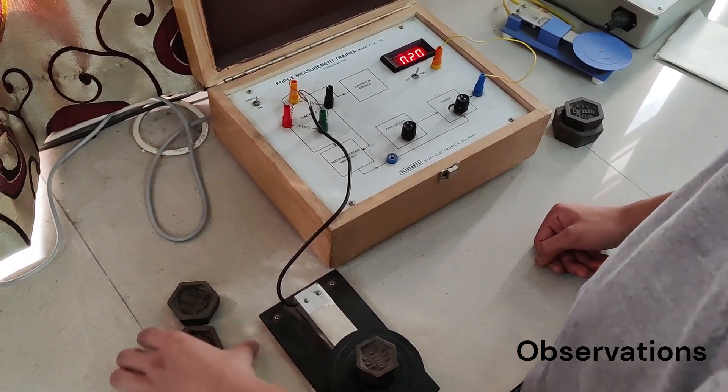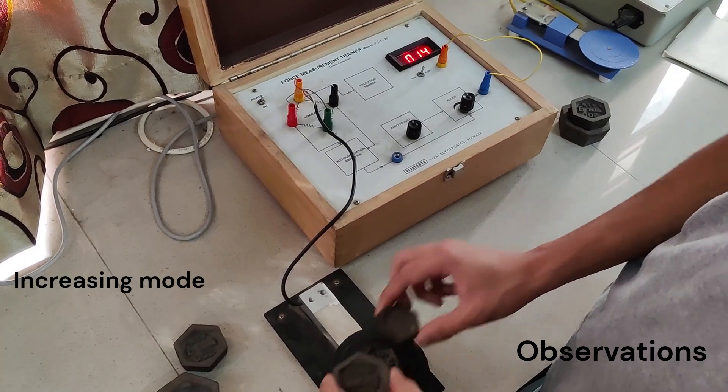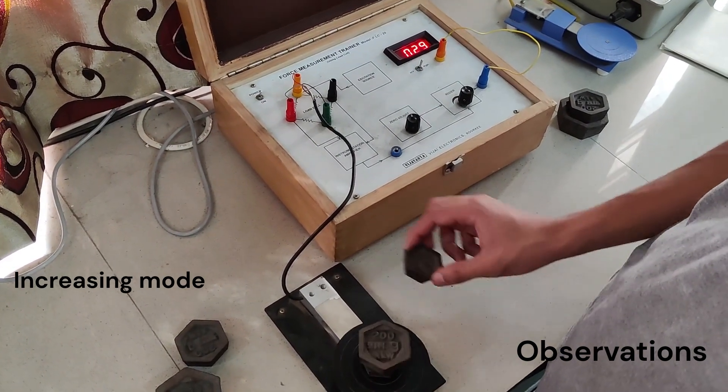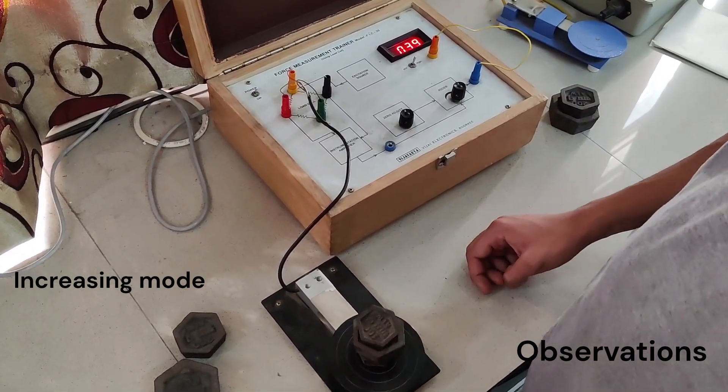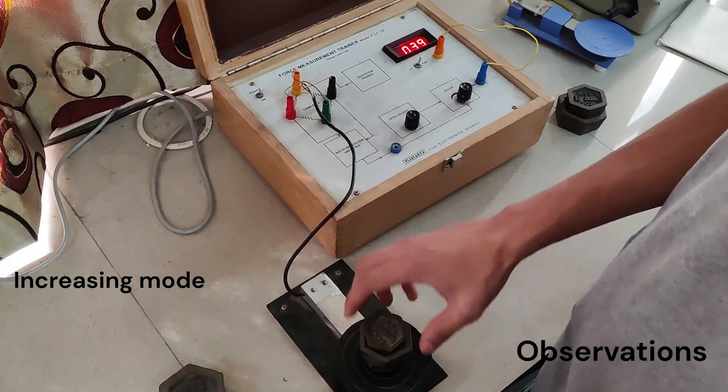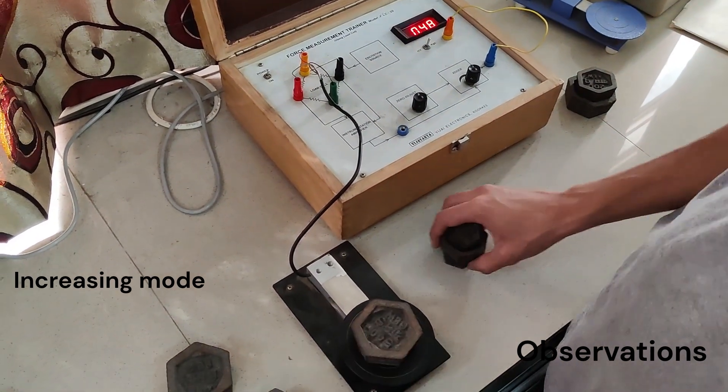Now that the load cell is calibrated, take readings in increasing mode and decreasing mode. In each mode, increment or decrement by 100 grams.